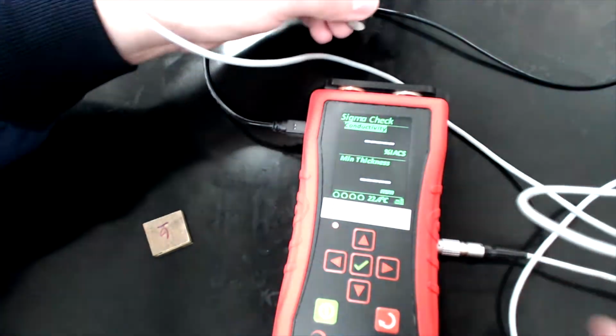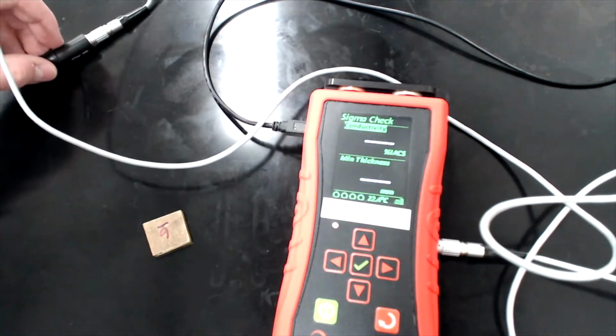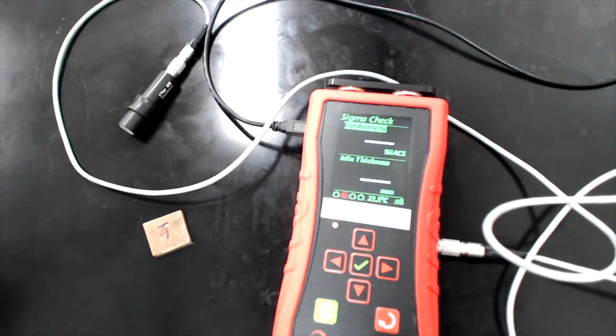8.46 or 47. And again, this should be 8422. So this one was actually pretty close. You can check these, and it takes a matter of seconds to check them. So you want to frequently check those standards to make sure that the calibration is the same, it's not drifting. You can check this periodically, especially if you're testing samples over a prolonged period. So just make sure you check that probably before and after to make sure that there's been no drift. And in this case, I might go back and change the calibration.